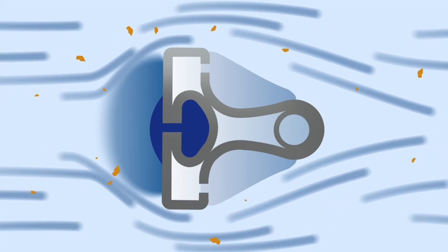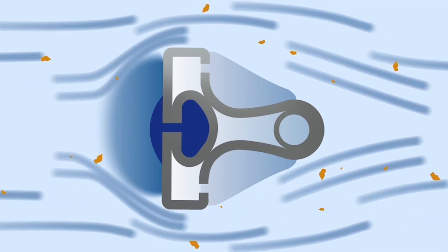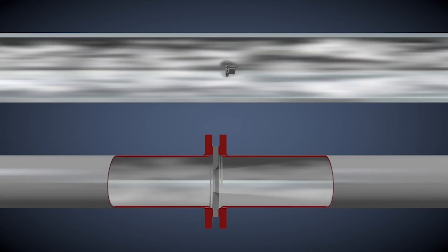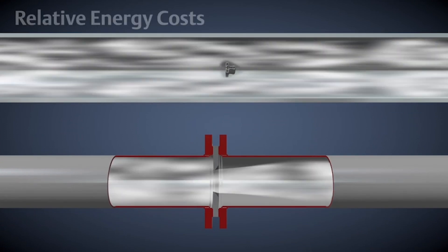Sensor shapes other than the T-shape will have a lower signal strength and will not perform as well over a wide turndown. The Annubar sensor creates a small profile within the pipe, resulting in less permanent pressure loss than other flow technologies like orifice plates or venturis.